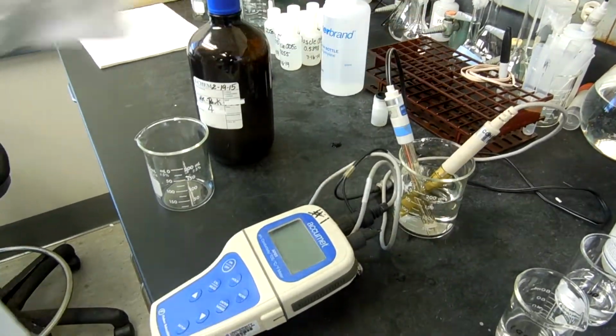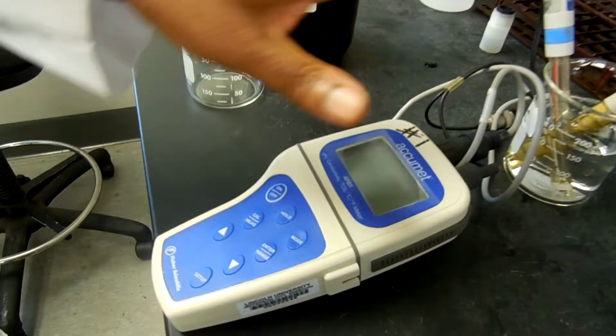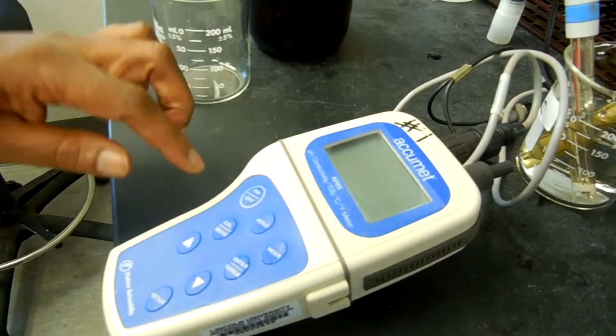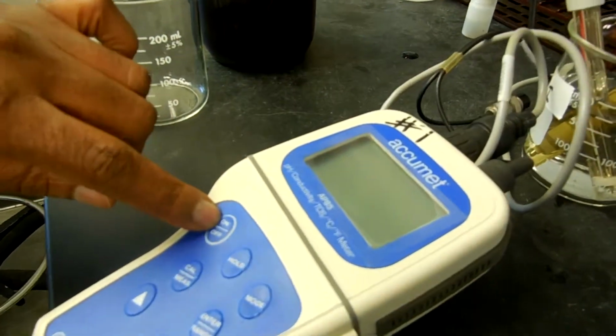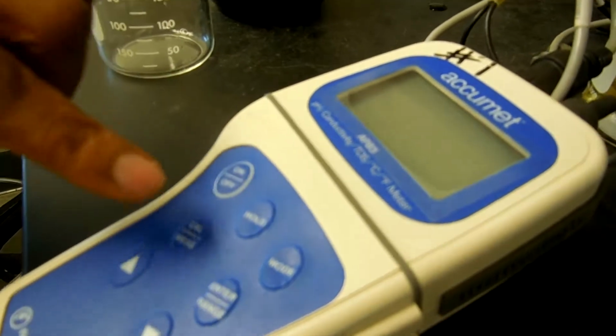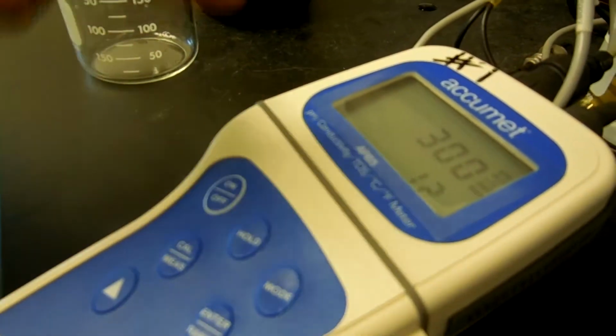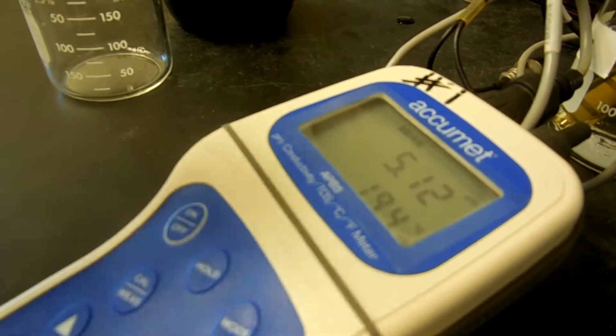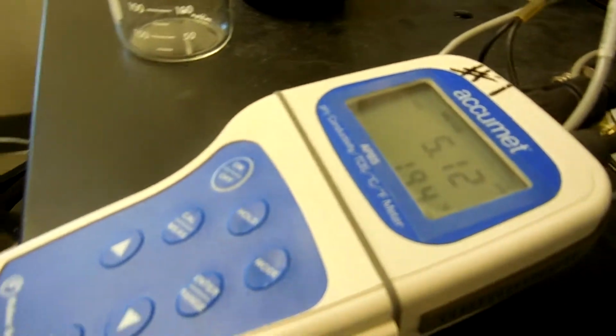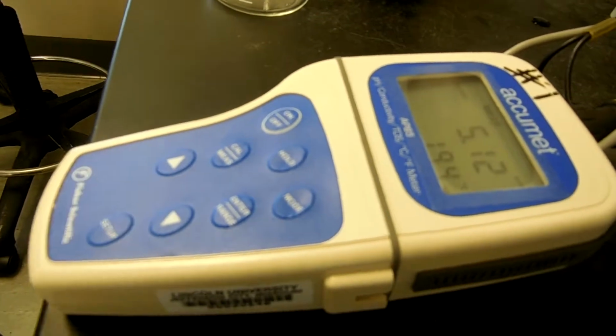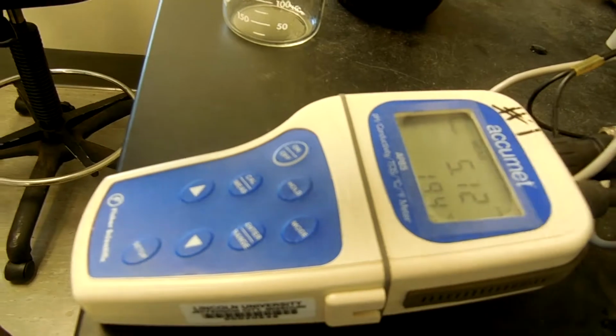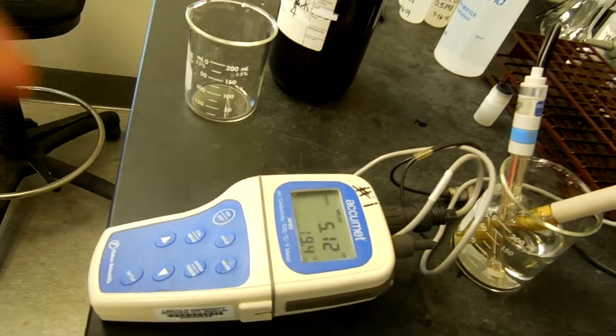Once you are ready with all this and they are connected well, you press the on button. This button has an on and off. You press the on button, then hold on and allow the instrument to stabilize. After that, you rinse out the electrodes, and then you are ready for calibration.